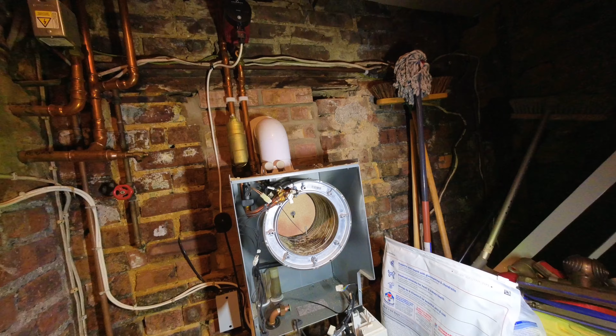I thought it was a system boiler, but it's not - it's a heat only boiler, so there's no expansion vessel to recharge. The whole system is still maintained as an open vent system. It's going to be a pretty straightforward service in that respect. Let's get this cleaned out and then pop it back together.